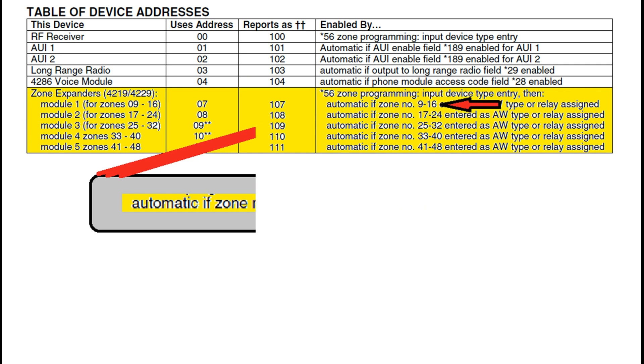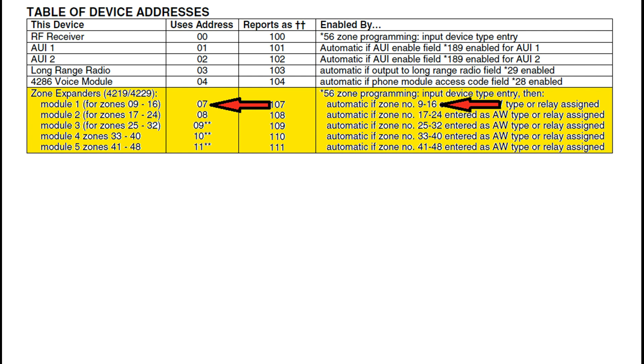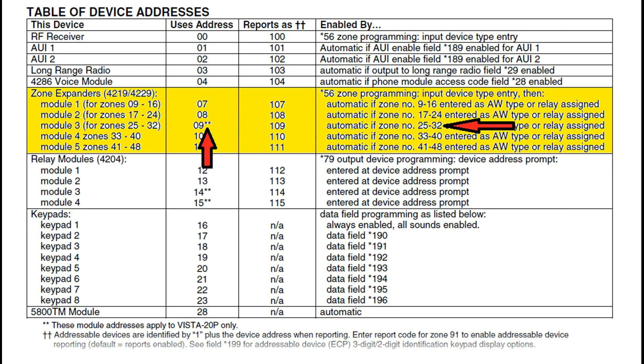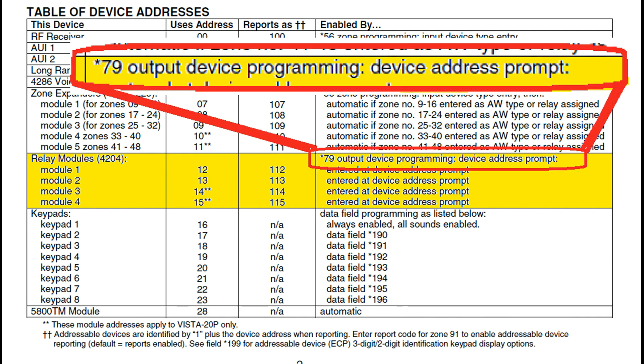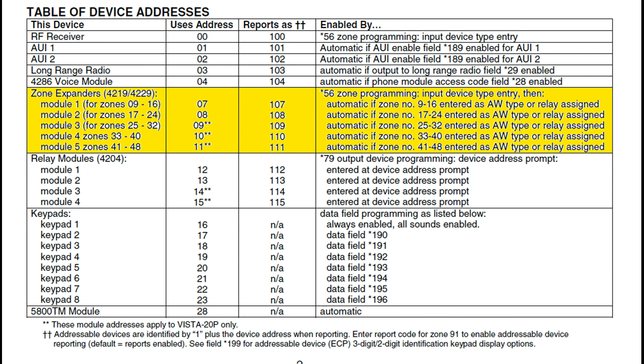This will automatically enable address 7. So zones 9 through 16 are address 7. Zones 17 through 24 is address 8 for your second expander module. And 25 through 32 should be address 9, but you need to pay attention to these asterisks — they indicate the address only applies to the Vista 20P. An older panel like a Vista 15 won't be able to do this. The next set of addresses are for relay modules: 12 through 15. These addresses are activated when you use the star 79 output device programming to set up each relay in the module. Some zone expanders actually have relays mounted on board them. So even if you don't use the zones in the zone expansion module, using star 79 to program a relay in the module will also activate that module's address.